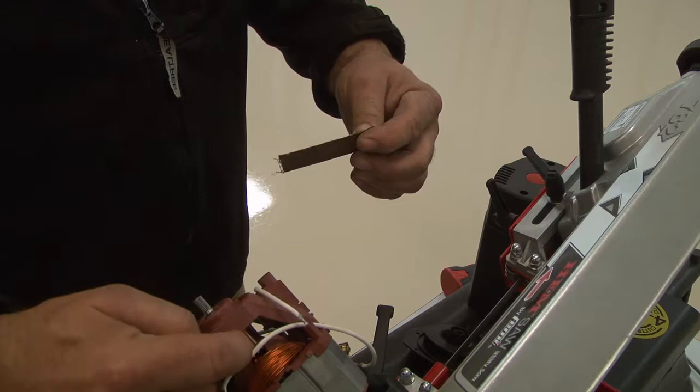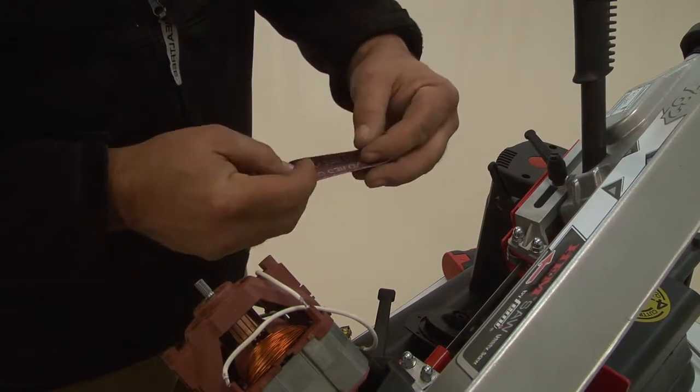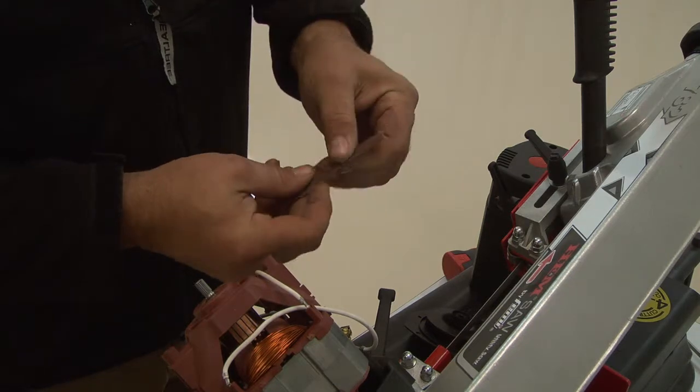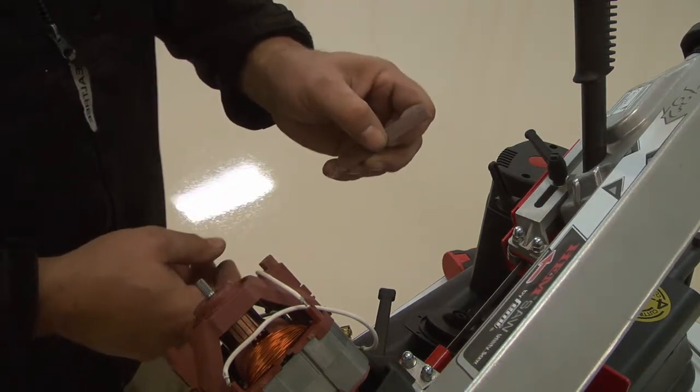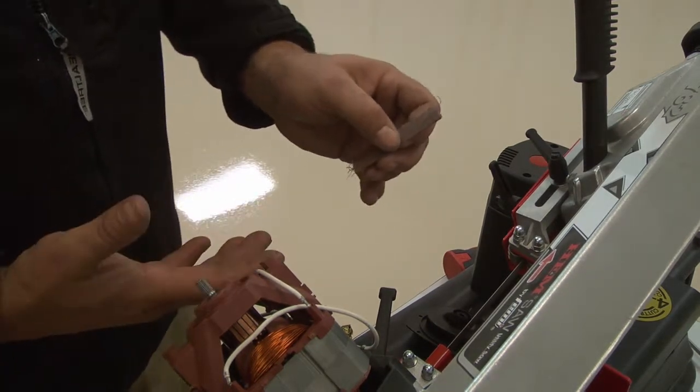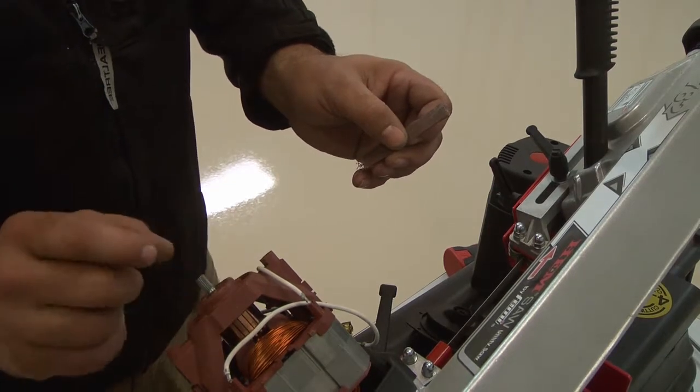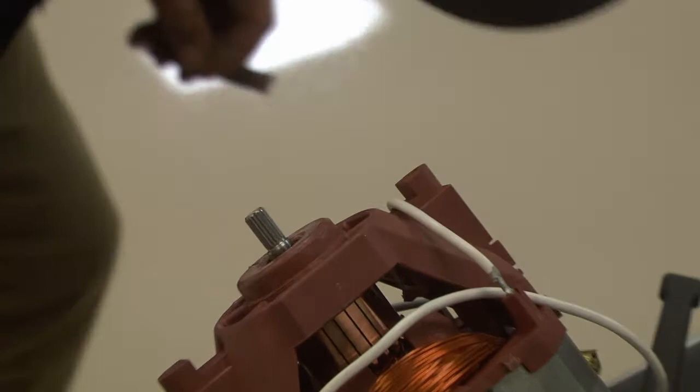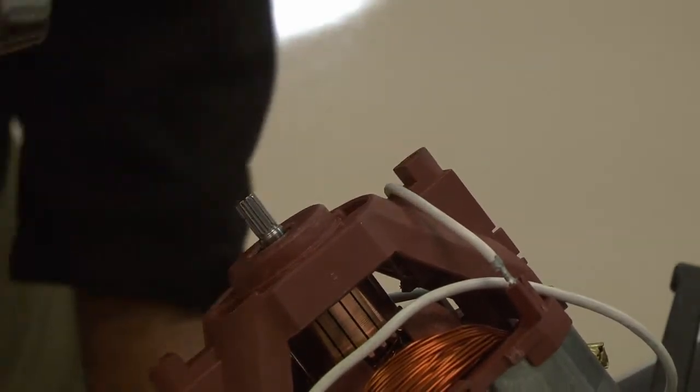The commutator is now exposed enough to enable cleaning. The motor shaft can be spun by hand, but it is more efficient to use an adjustable speed drill set on slow speed to spin the armature while holding a folded strip of fine grit abrasive cloth against the armature commutator.